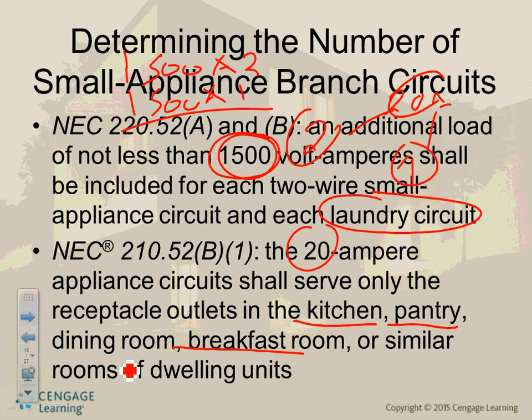So that 4,500 is added to the 30? Yes. 34. Yep. Absolutely. But then you don't do the math on it because the branch circuit is already sorted. We add them when we size the feeder and the service. Guys, remember, you need to size feeders and services and branch circuits. Well, the branch circuits are already sized. Here, 220, 220 here, and 120 here. Done. Now, how about the feeder and the service? We don't have a feeder. But how about the service? That's where this becomes a big deal for sizing a service. So you add these two numbers to the 30K to size your service.